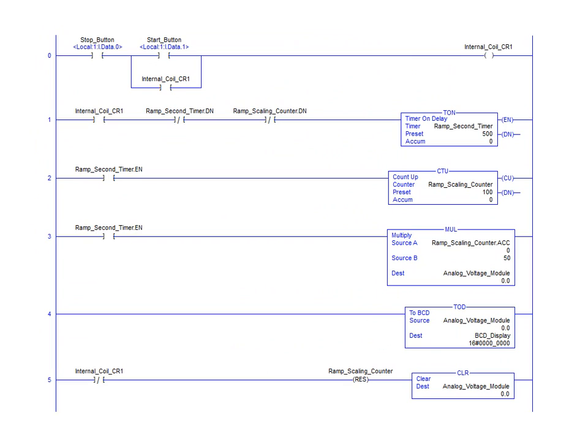We will begin by taking a brief look at our ramp voltage application. In this application, a counter is being incremented every 500 milliseconds. The accumulated value of the counter is being multiplied by 50 and sent directly to the slot 8 output module. As the preset value for the counter is set to 100, this will provide the value range of 0 to 5000 being sent to our analog output channel 0 location.